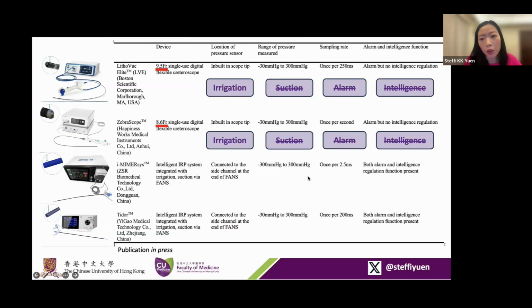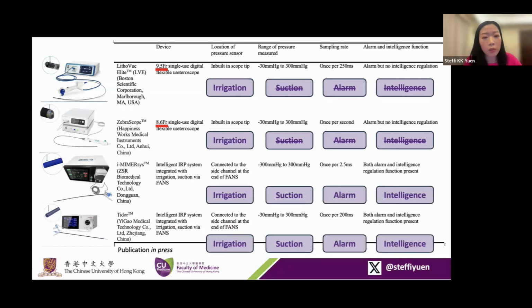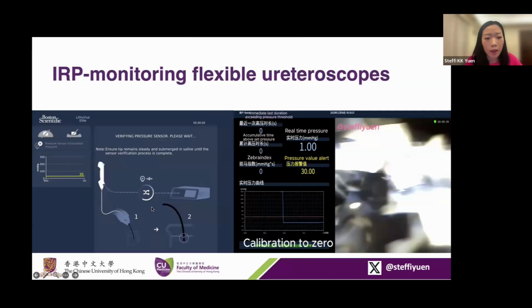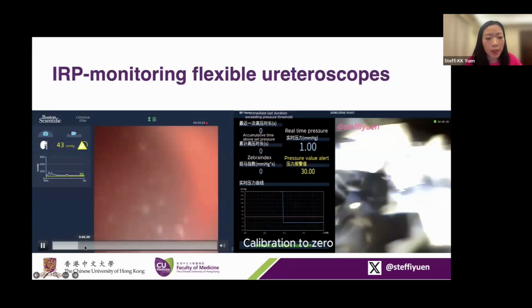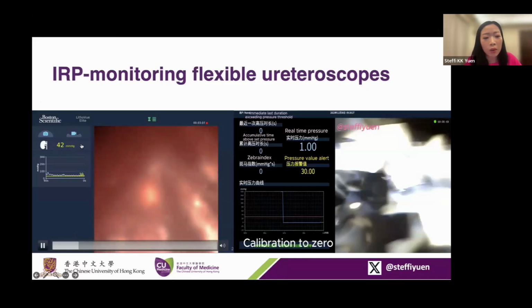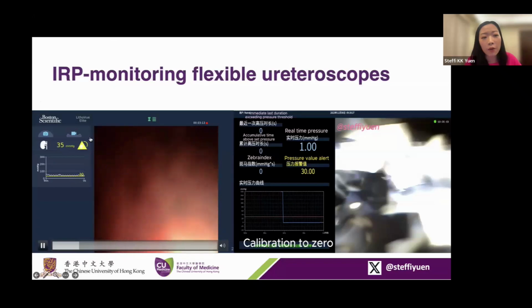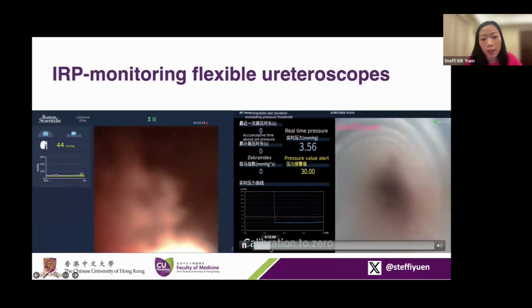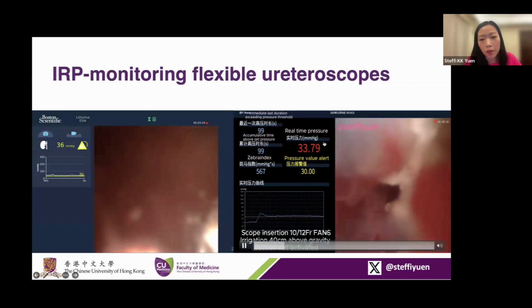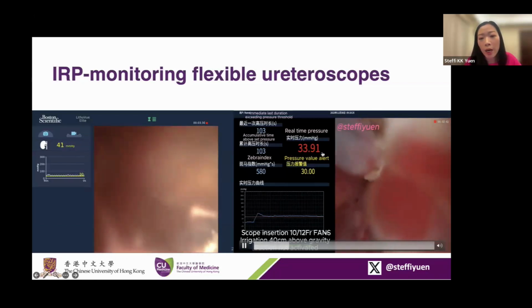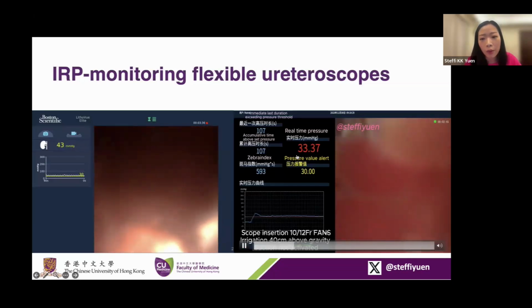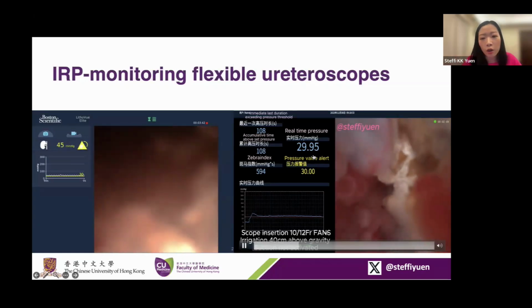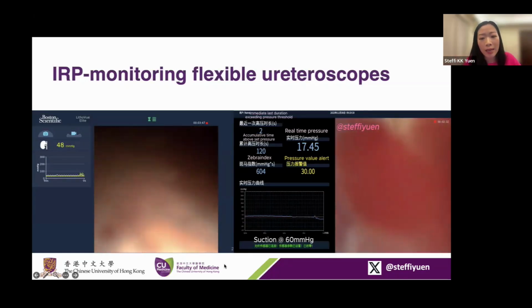There's alarm alert and also intelligence. As for the new systems, they measure IRP via the sheath, which is connected to the processor, and it has both suction, integrated irrigation that's connected to the scope, as well as alarm and intelligence. Ben has shown a lot of videos on the Elite system, but I would just like to draw your attention that there's only a flashing yellow triangle when it's above the set value of 30 millimeters of mercury. On the right side, I'll show you the Zebra scope. If you see the red value, the real-time IRP is more than 30 millimeters of mercury, which is the set value, and it's only flashing in red. There's no intelligence or feedback mechanism as to how to regulate it back within safety limits.